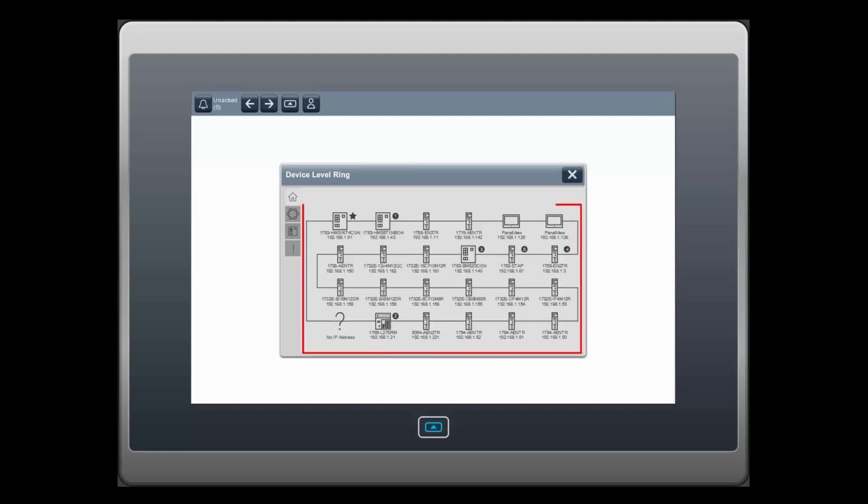The Home tab screen displays an auto-generated network layout. This example is displaying a 24-node network. Number and sequence of nodes is based on the information provided by the active device-level ring supervisor. The active ring supervisor is always located on the upper left position of the screen, and is identified by the star icon at the upper right corner of the node.